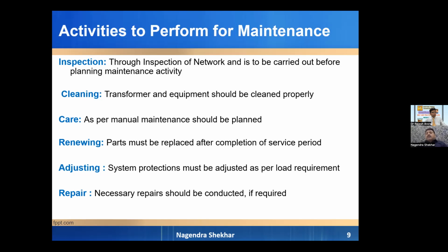So what do we do while performing maintenance? First of all, inspection. For any kind of maintenance, we inspect the entire network. So what kind of maintenance is required? As I told you, partial discharge or thermoscanning of a network is basically inspection. You are inspecting where faults are developing and what remedies you can provide to that developing fault so that it should not turn into breakdown. Cleaning. Cleaning is the most essential part of any electrical distribution network. It includes our equipment like switchgears, transformers, lines, insulators. These should be properly cleaned after an interval because dust itself causes many breakdowns.